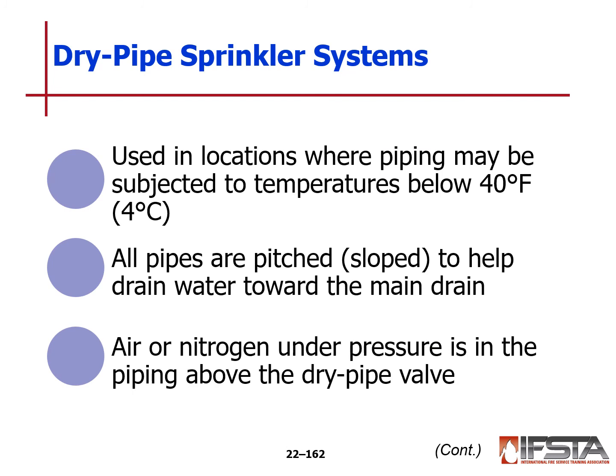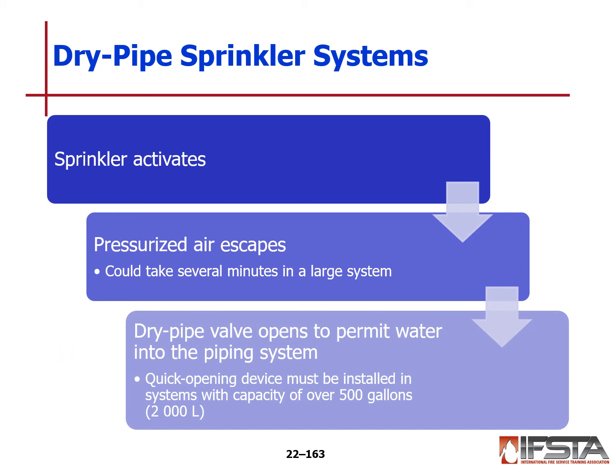Again, dry pipes are used in locations where piping may be subjected to temperatures below 40 degrees. All pipes are pitched or sloped to help drain water towards your main drain. Air or nitrogen under pressure is in the piping above the dry pipe valve in a dry system. So when a sprinkler activates, the pressurized air escapes, which could take several minutes in a very large system. The dry pipe valve opens to permit water into the pipes. A quick opening device must be installed in systems with capacity of over 500 gallons.